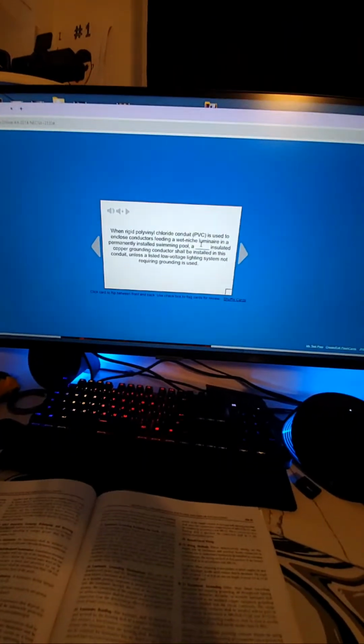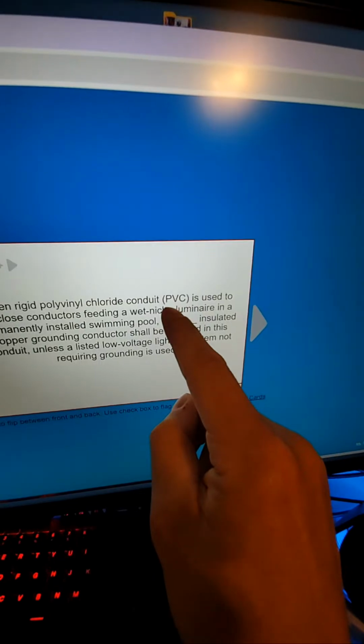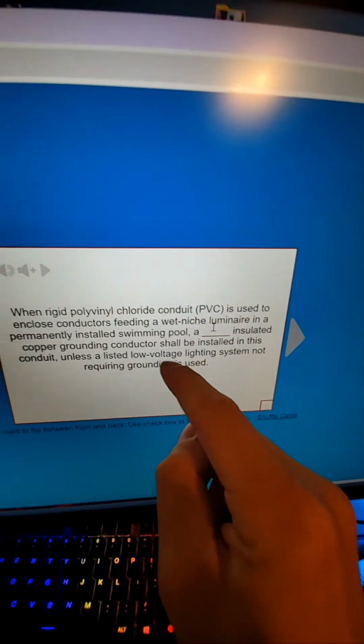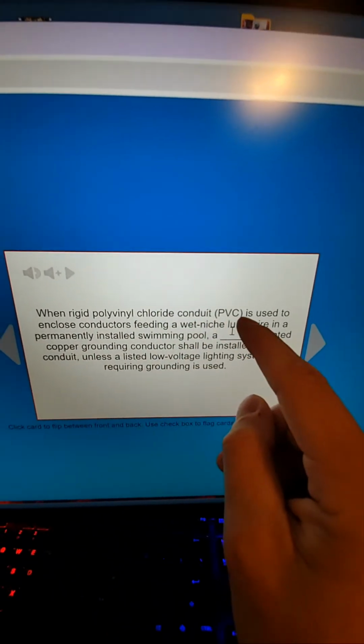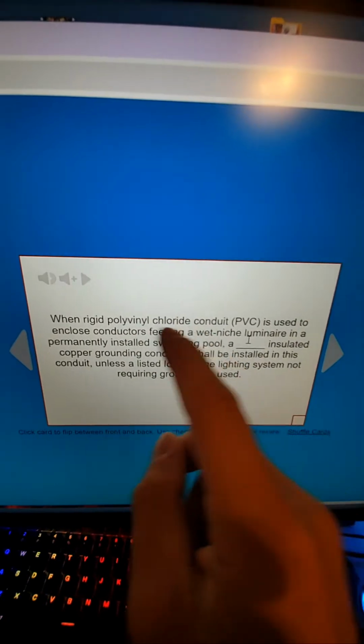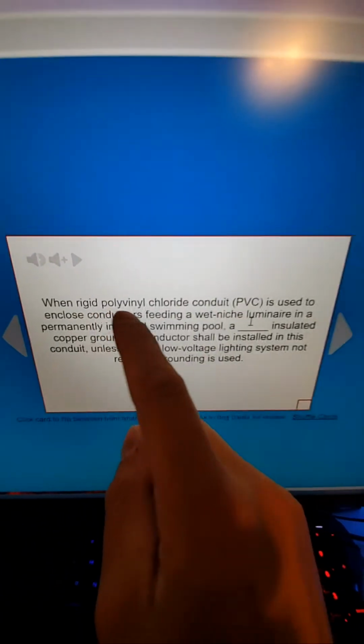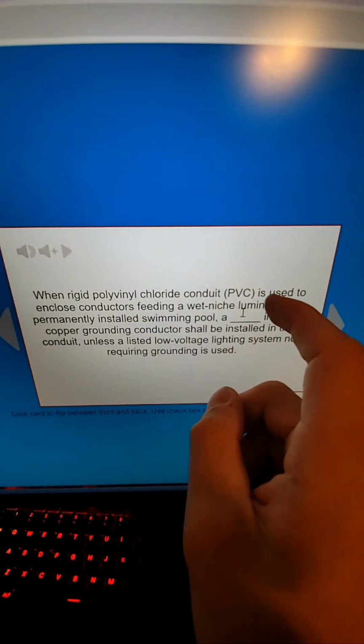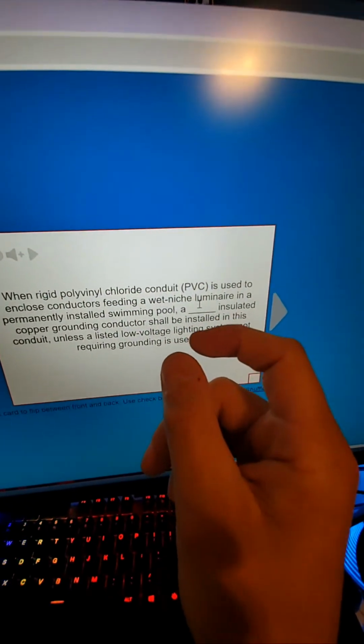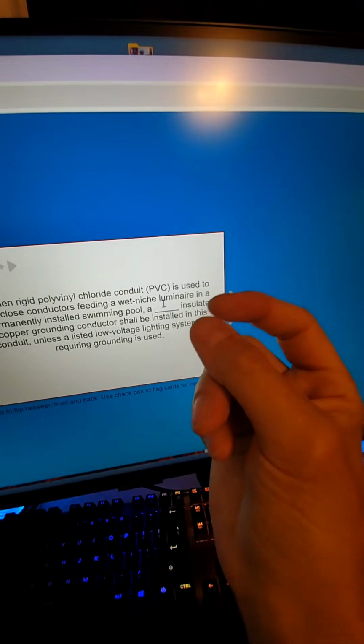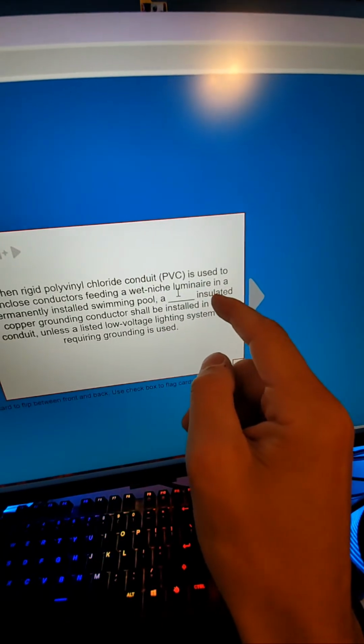So if you've got a PVC, right, if you had red brass, which is conductive, you're not required to do this. But because you've got PVC, and they called it rigid polyvinyl chloride, that way you'd think it was rigid metal. So they do this purposely, right? This is just PVC. And it encloses the conductors, which should be the cord that comes off of that light assembly. There's going to be a lug inside of your light. You need to run a number 8. And it's got to be insulated there. See? Insulated. And you're going to run it on a lug inside of that light with the cord.